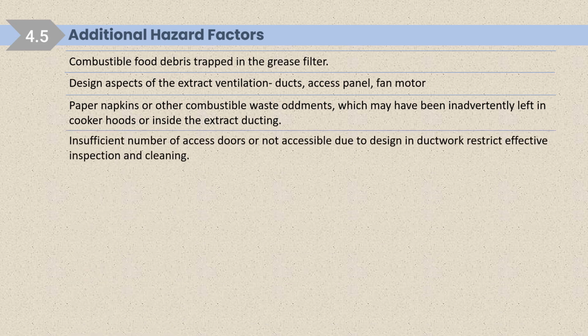Insufficient number of access doors, or not accessible due to design in ductwork, restricts effective inspection and cleaning. Suppose there is no access panel in the duct or near the hood where grease can be trapped, and it may cause fire. So it restricts effective inspection and cleaning. We are not able to identify where it is accumulated, where it is trapped, and with time it may cause fire also.